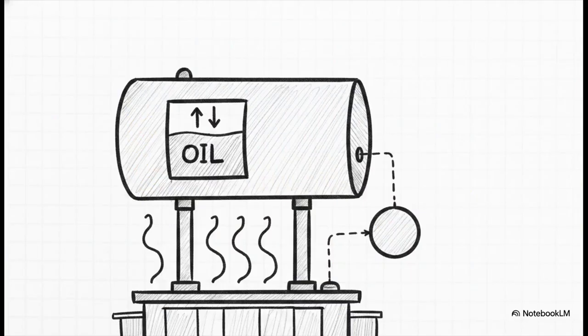That's the conservator tank. You see, when a plant is running at peak production, this transformer gets insanely hot, and the oil inside physically expands. The conservator tank gives that oil the breathing room it needs. And hey, if the pressure ever spikes dangerously high, a pressure relief valve, or PRV, will vent it out so the whole tank doesn't just rupture like a giant firecracker.